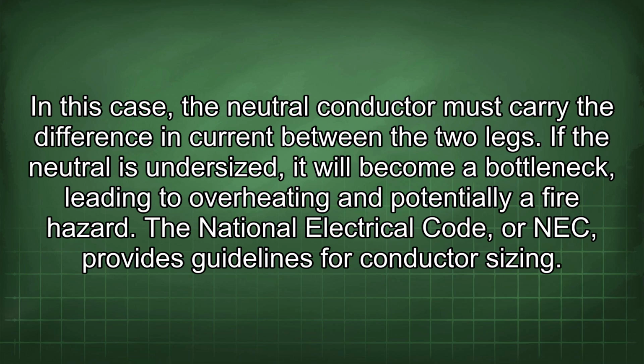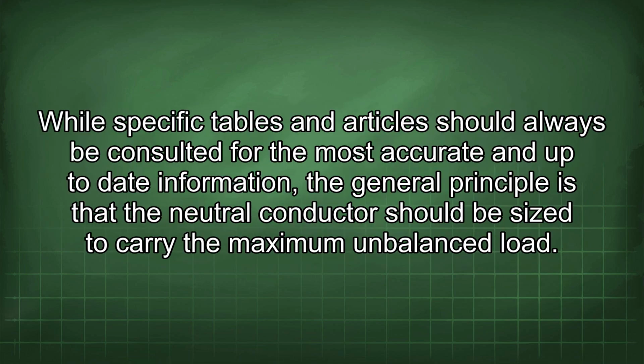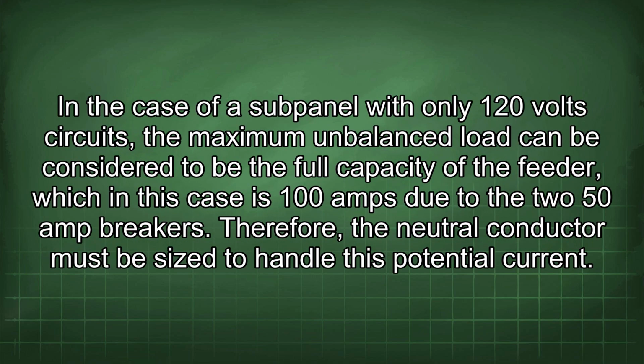The National Electrical Code, or NEC, provides guidelines for conductor sizing. While specific tables and articles should always be consulted for the most accurate and up-to-date information, the general principle is that the neutral conductor should be sized to carry the maximum unbalanced load. In the case of a subpanel with only 120-volt circuits, the maximum unbalanced load can be considered to be the full capacity of the feeder, which in this case is 100 amps due to the two 50 amp breakers. Therefore, the neutral conductor must be sized to handle this potential current.